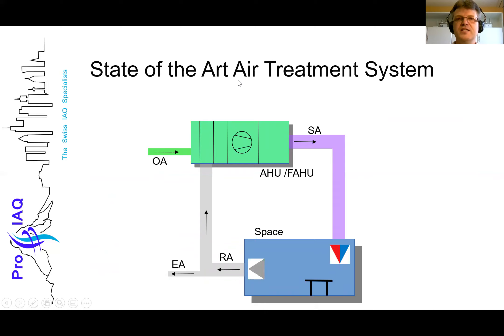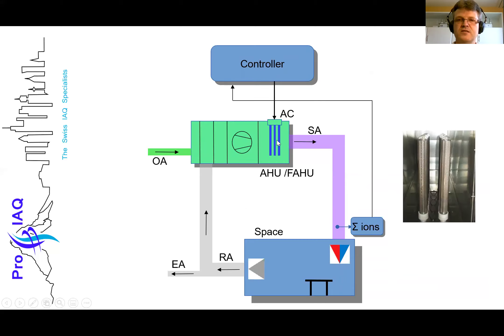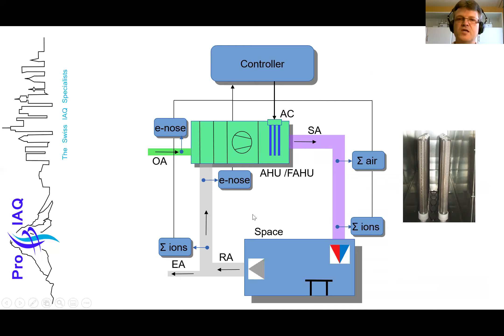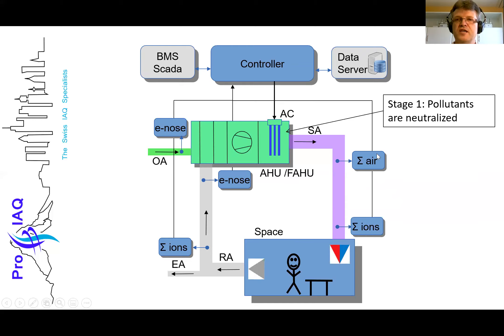How do we work inside the space to improve air quality? This could be a ballroom, a hotel lobby, or an airport terminal. We have the fresh air handling unit, supply air duct, and return air duct — we might have recirculation. By adding a bipolar ionization stage into the last stage of the air handling unit or inside the supply air duct, we start the activation process. If the process is very dynamic, we can use more sensors to totally understand what's happening — seeing the air quality entering and being returned from the space.